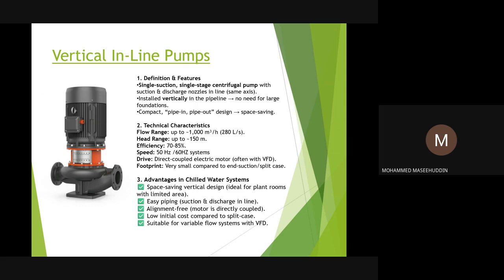And even the maintenance is very easy for these types of pumps, because you don't need to disturb the piping, because it is an inline pump. If you see in the picture also, the suction and discharge are in one line, and you can easily connect it to the chill water pipe. This pump which you are seeing in the picture is without VFD.